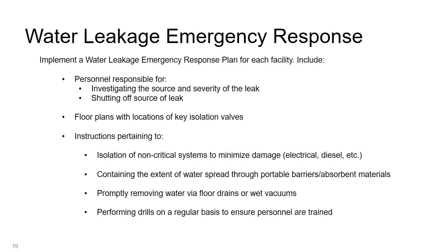In the unfortunate case where a leak or release does occur, having a formal, written, and rehearsed plan is critical to minimize damage. Here are some of the key aspects to consider. There should be a designated personnel to perform each task. This will help to clear up confusion that may result in a crisis by having people who are trained for each function, such as a leader, valve isolator, someone to get the crash cart. The appropriate action can be performed promptly, minimizing damage as a whole.